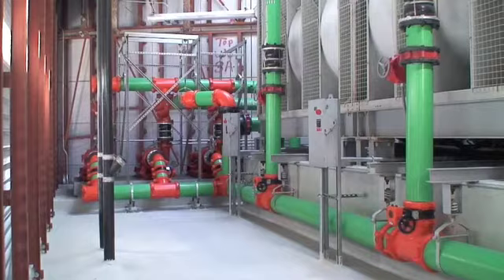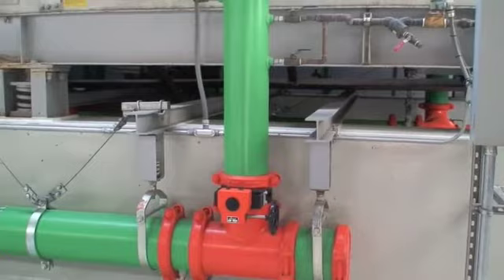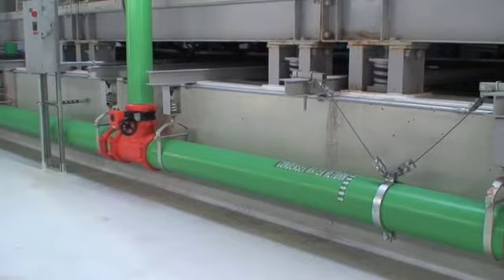You were just showing us the cooling tower. One of our building engineers saw a sewer bill come in — sewer is basically billed on whatever your intake is, and they bill that as an outtake. We found out that we were losing a lot of our water through evaporation in the cooling tower. So the engineer put water meters on the intake and on the outflow and took that variance. We went to the local water company, PG&E, and they rebated us $20,000 for the previous three years, and reduced our sewer bill by $10,000 a year — because the water is going up through the cooling towers in evaporation, not through the sewers.